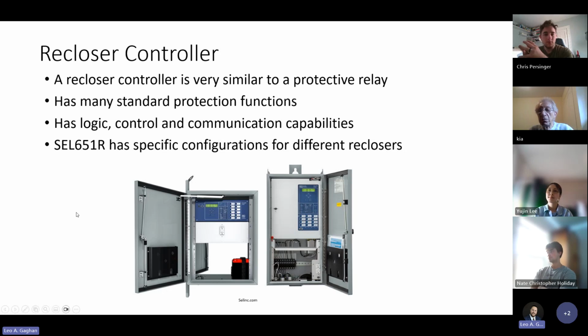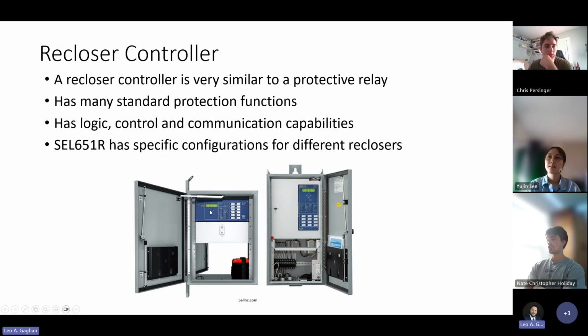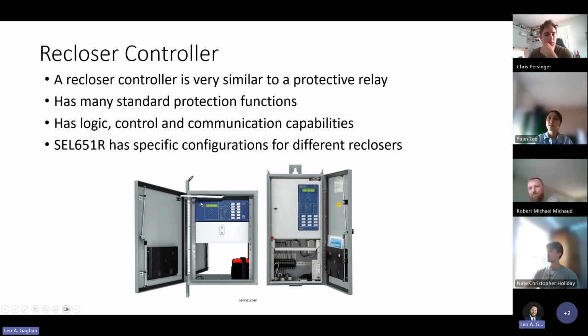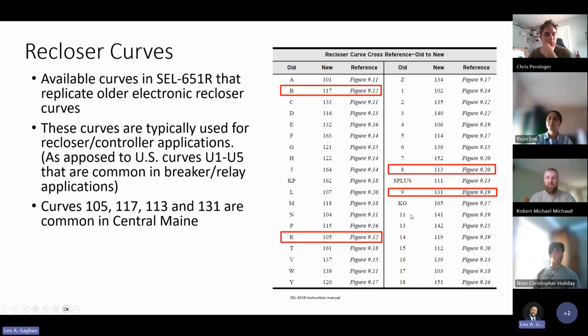This recloser controller is very similar to a protection relay, kind of like one of the ones you would see in the lab. It's got some unique features that make it just a little different at times, but at a fundamental level it's very similar. You can even see it looks similar. Reclosers have some unique curves you probably wouldn't find in a 421 or 451. They're really meant to mimic some of the older electronic reset reclosers, which even those were meant to mimic some of the way older electromechanical type characteristics.